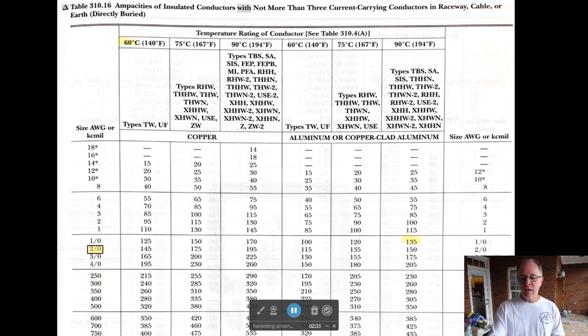We've got to find THHN. If you look in the 90 degree Celsius column, it is there. So now we see it's 195 amps—that's what the 2-Aught will carry. This is what you do on every wire. If you're looking for 6-THW, you'll go to 6, find THW, which is in the middle column, and it's 65 amps.